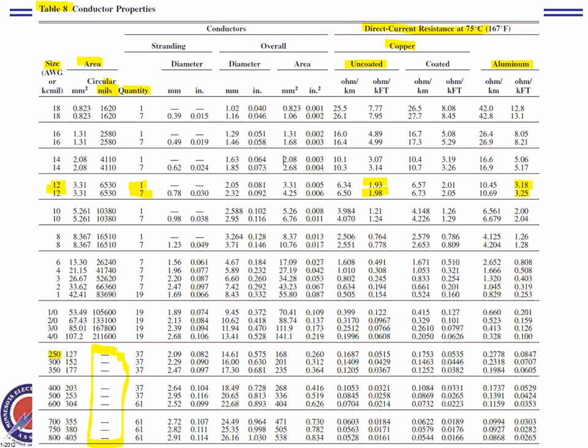As long as we're on this table, guys, I want to bring to your attention a couple of other things. The diameter here and the area. We use this one later when we size conduits. We use the diameters when we size cable trays, and the cross-sectional area when we size conductors. That's it. That's how you find the resistor. Now we're focusing on the resistor. Okay. How about the circular mil? You need the circular mil for number 12. Can you see the circular mil 65, 30, 65, 30? Same. The impedance is different though. All right, everybody got that table? What you need from the table?